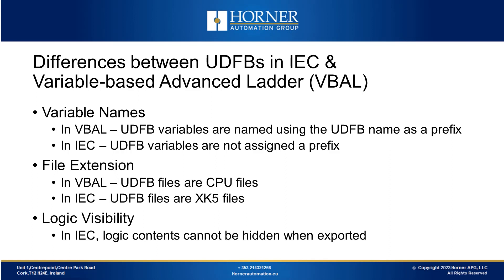For example, if your UDFB is named convert and you have a variable called enable, in the variable-based advanced ladder, this variable becomes convert.enable. But in the IEC editor, we don't add them. Unlike subroutines, a variable like enable stays as enable. But it's important to know that if you use the same variable name enable in other parts of your program, there might be problems because of this naming style in IEC.